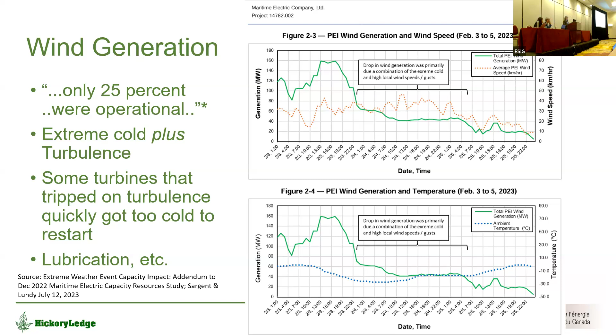So lubrication is an issue because wind speeds were pretty good, but you can see the wind tripped on turbulence and basically couldn't get back going again. They also tripped out on low voltage lockouts. This is kind of interesting: they would trip for lubrication issues, but because the wind is at the end of a radial line, the act of them tripping reduces the voltage, and then they couldn't start because voltage was low. So it was kind of unfortunate.